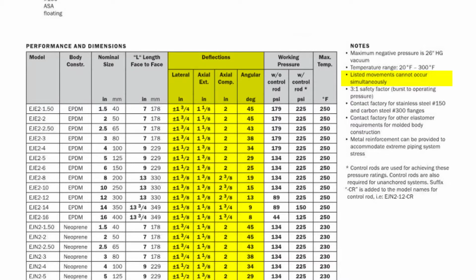The next section of columns indicates the maximum amount of movement in the various directions that each model can accommodate: lateral or side-to-side, axial extension and compression, and then angular, where the axis of one end is not in line with the axis of the other end. Note as well that the joint cannot accommodate these maximum deflections simultaneously. These columns highlight the functional differences from flexible metal hose connectors, which cannot allow angular or compression or extension movement.